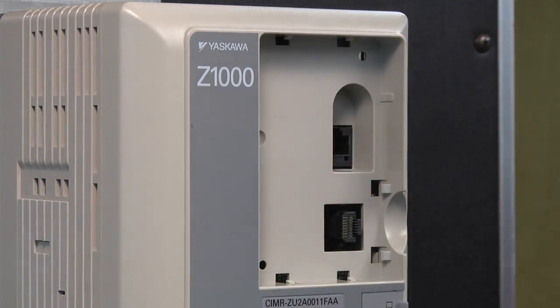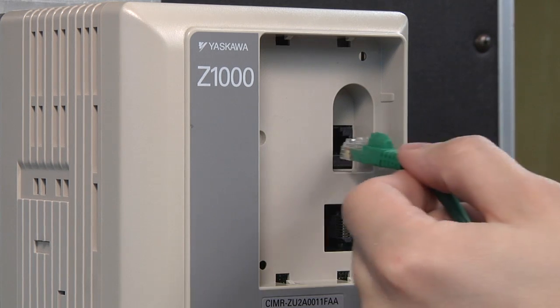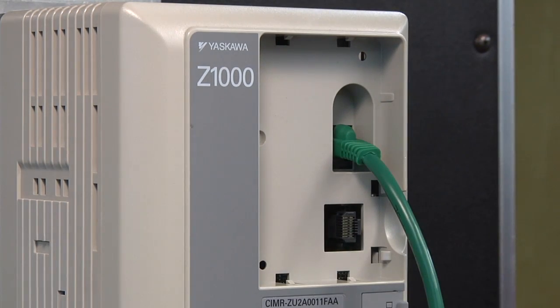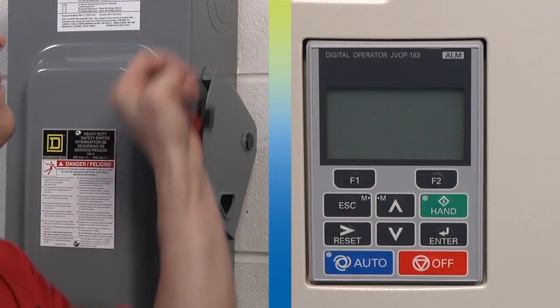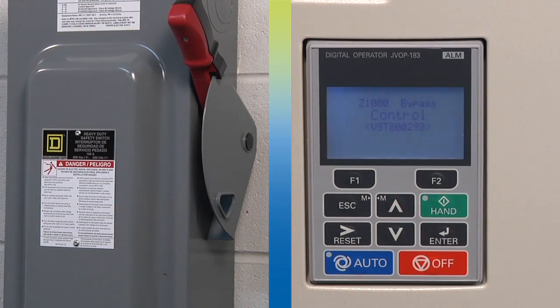When the cable is connected to your computer, remove the digital operator. If you have a smaller bypass, there may be a dummy operator you need to remove. Connect the other end of the boot flash cable to the connector on the drive's control board. Now you're ready to power up the drive.